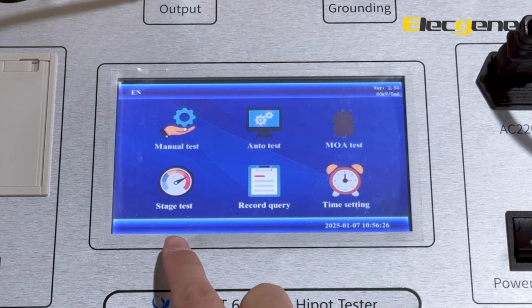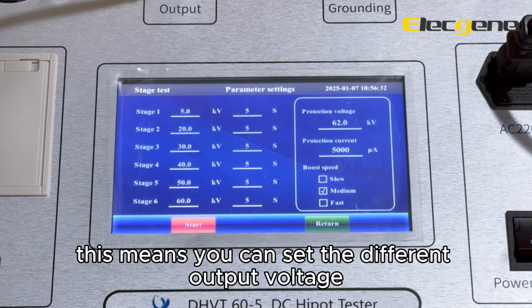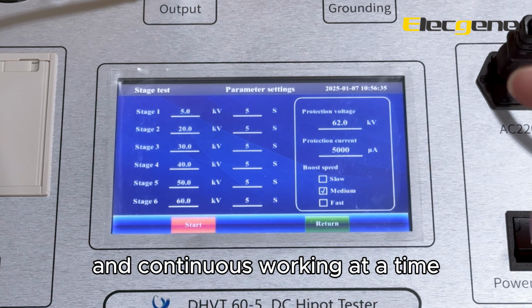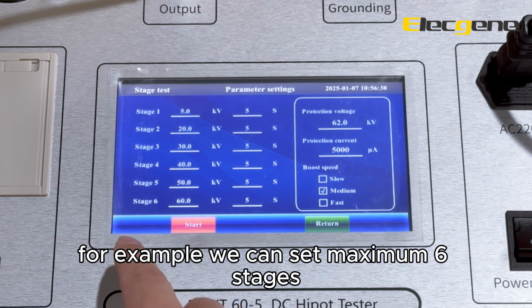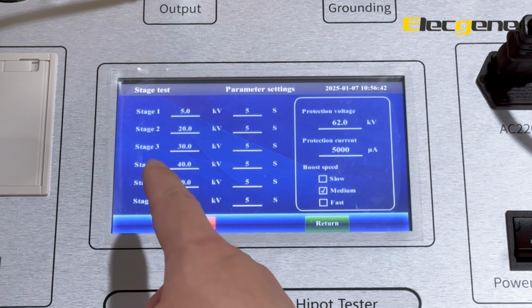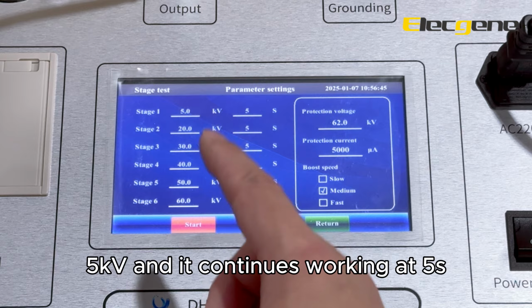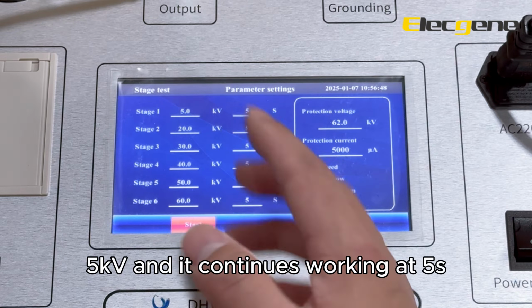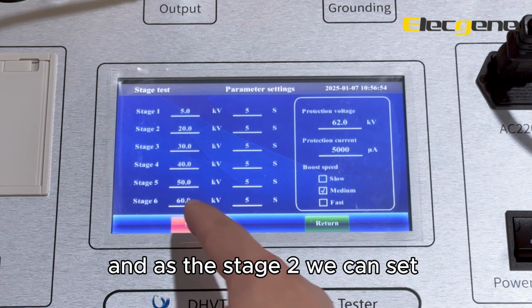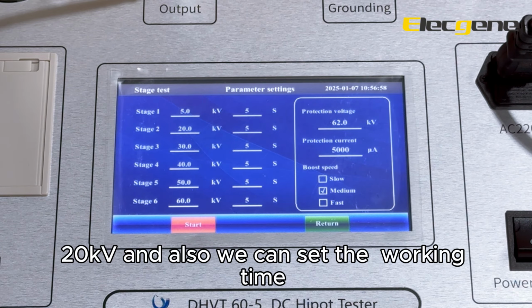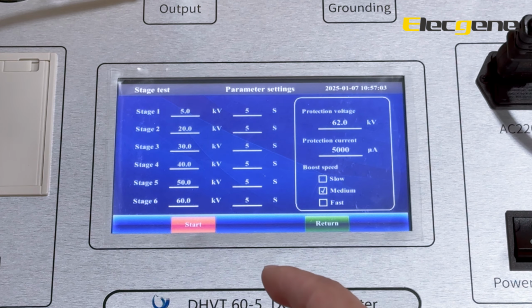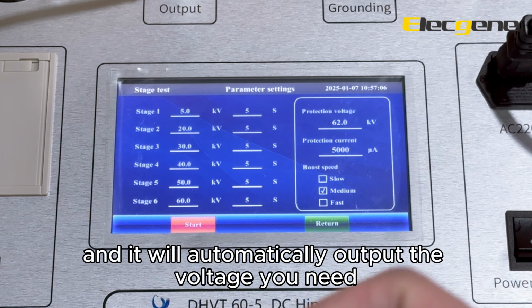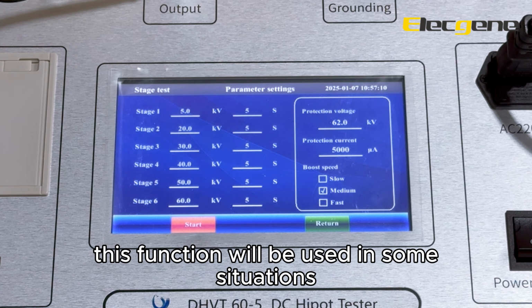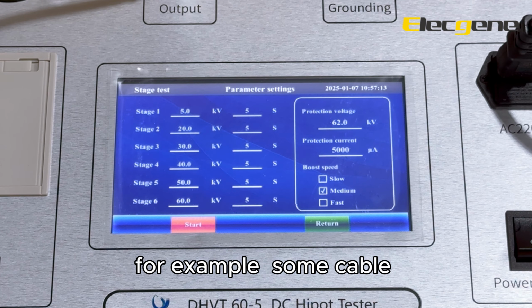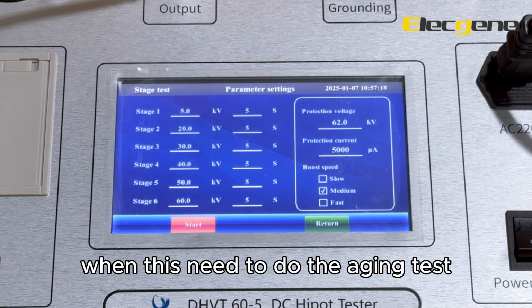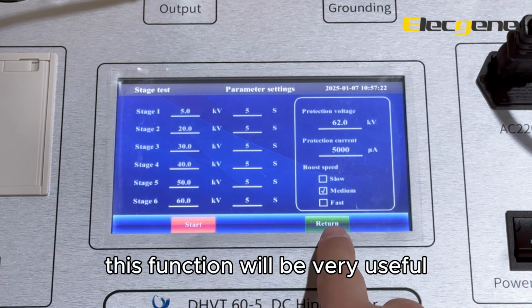And this is a stage test. This means you can set different output voltages and work continuously at each one for a set time. For example, we can set a maximum of 6 stages. For example, at the first stage, we can set its output voltage to 5 kilovolts and it continues working for 5 seconds. Here we can set other times. And at stage 2, we can set 20 kilovolts and also set the working time. After this, we press start and it will automatically output the voltage you need. This function may be used in some situations. For example, for some cables that need an aging test, this function will be very useful.